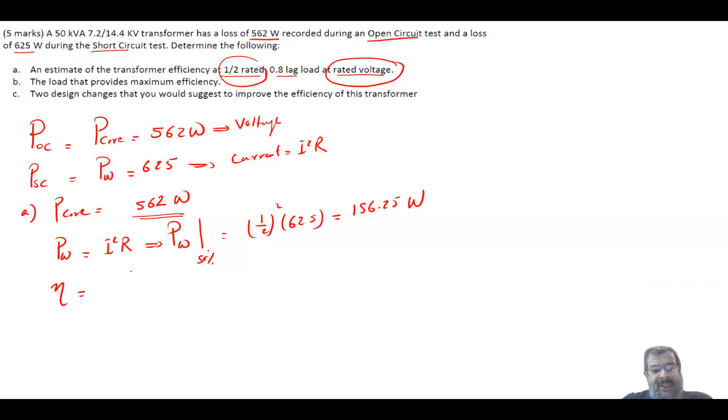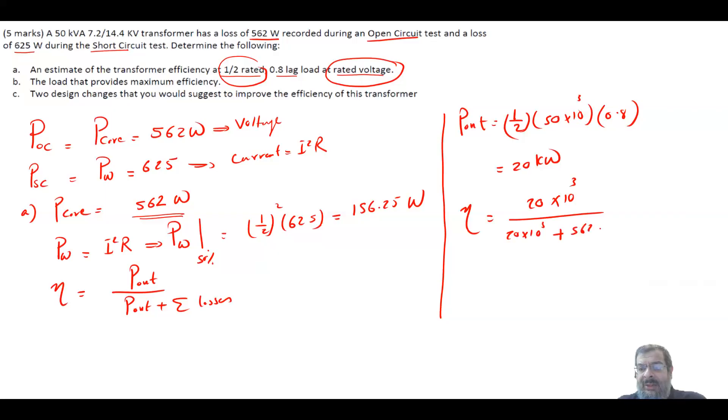Now, what is the efficiency? The efficiency is Pout over Pout plus summation of the losses. We know the losses, we need to find Pout. What is Pout? Pout is equal to one half, because it's half the load, times the kVA rating, which is 50 times 10 to the power of 3, times the power factor, which is 0.8. That is your power, which is equal to 20 kW. So your efficiency is equal to 20 times 10 to the power of 3, divided by 20 times 10 to the power of 3 plus 562 plus 156.25, times 100. And this will give me an efficiency equal to 96.53%.